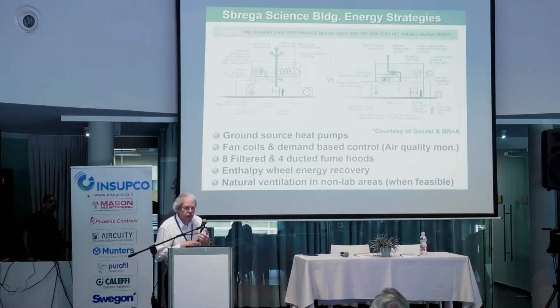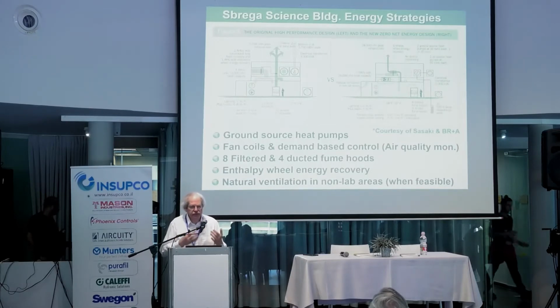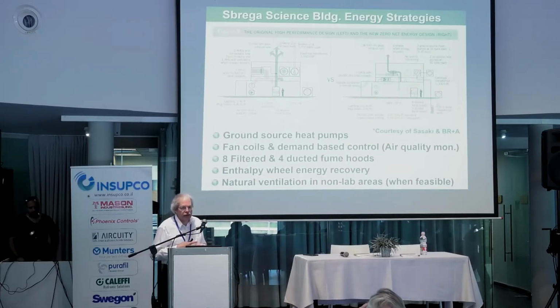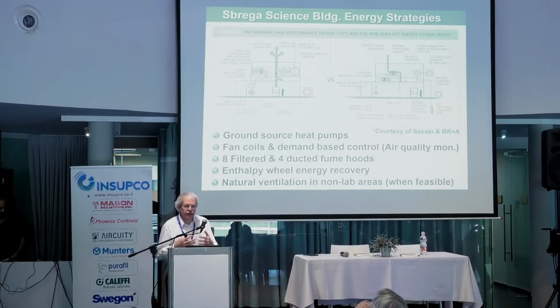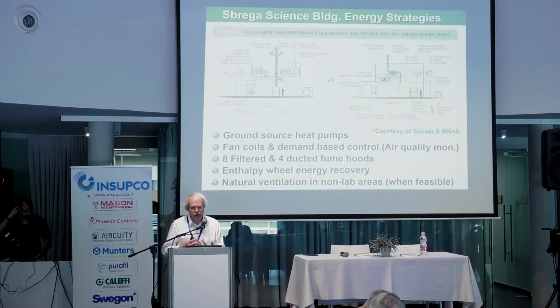It's not for cooling, and the cooling is done with, in this case, just a regular fan coil. So versus using a chill beam, they're using fan coils. But the same concept. This is the way they can reduce the airflow requirements. So they're just bringing that air in for makeup. And then they've been able to reduce the air change requirements by using a demand-based control system again, like we talked about before, air quality monitoring, an Aircuity type system.